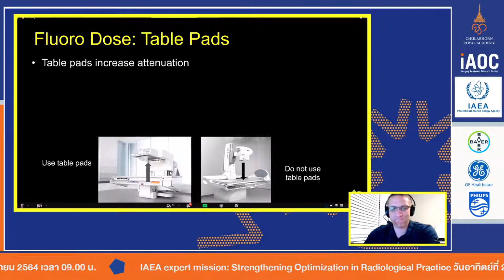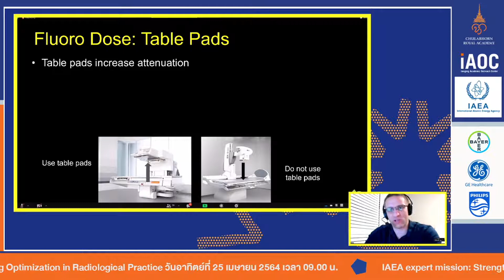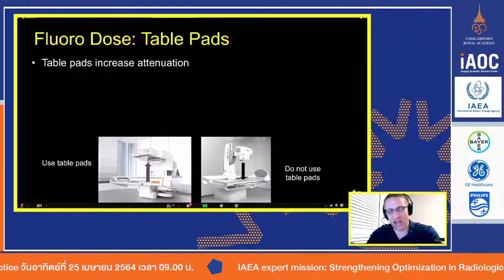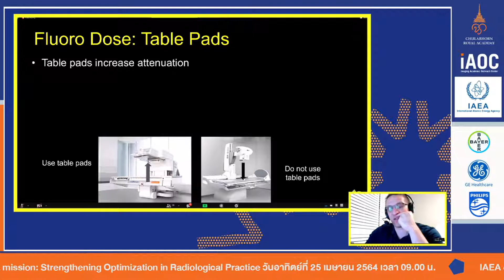Okay, on these tilt tables, and to a lesser degree some of the interventional systems, well, I guess I'll just say in general, these table pads, when we put patients on the pad, they're meant for comfort, right? But the pads absorb radiation. So if they absorb radiation, the system needs to put more radiation out to get the same dose to the detector.